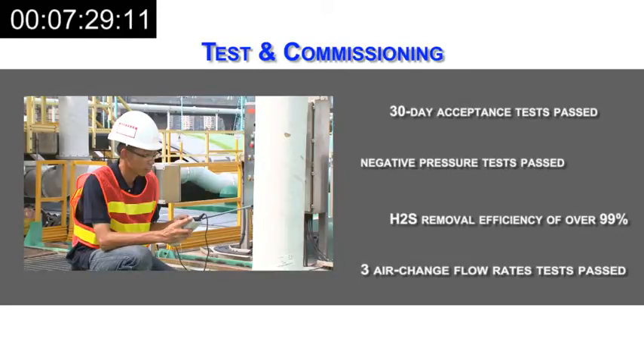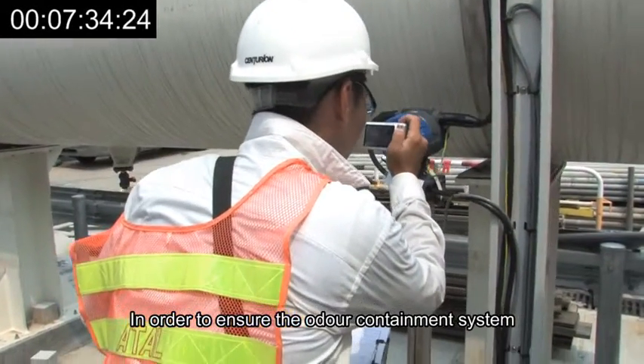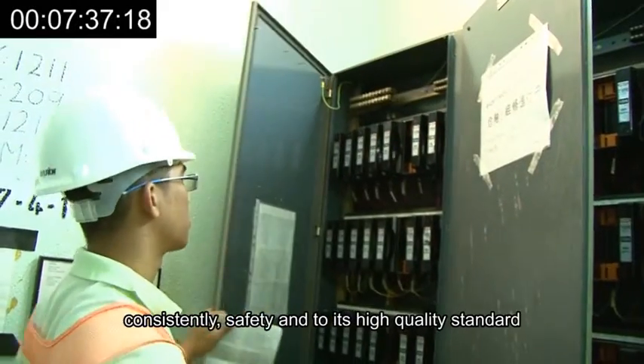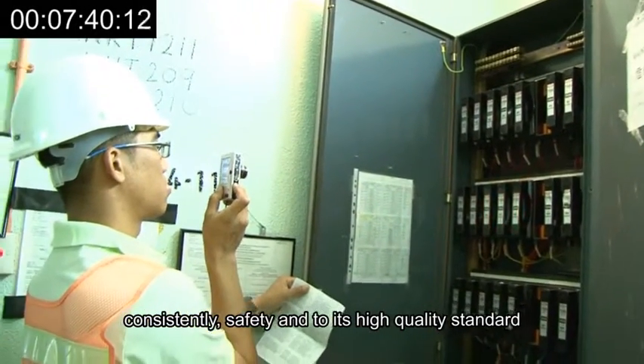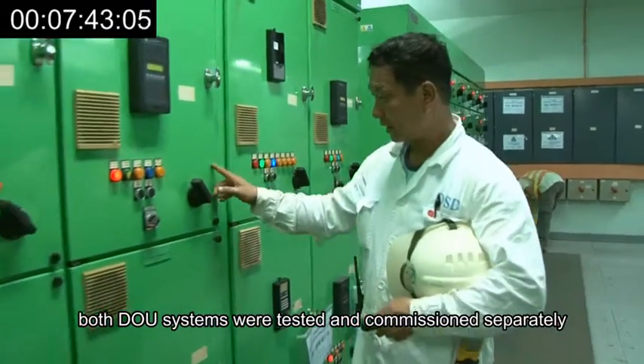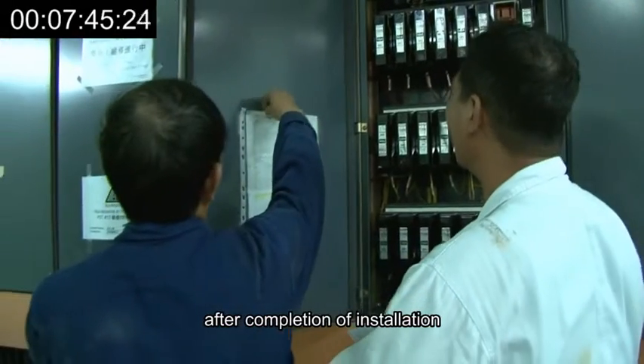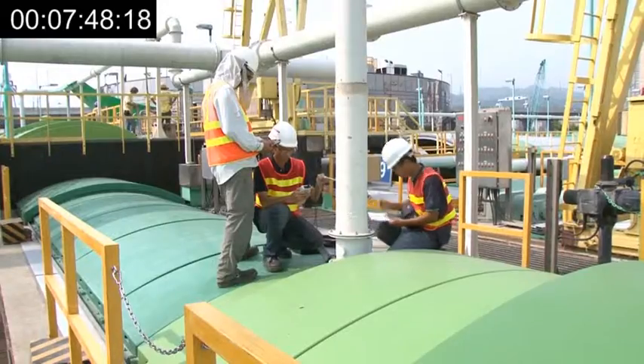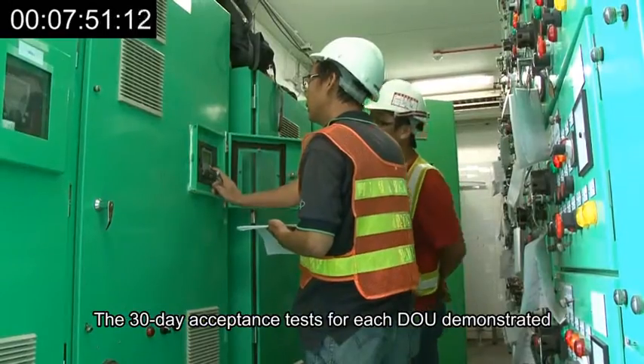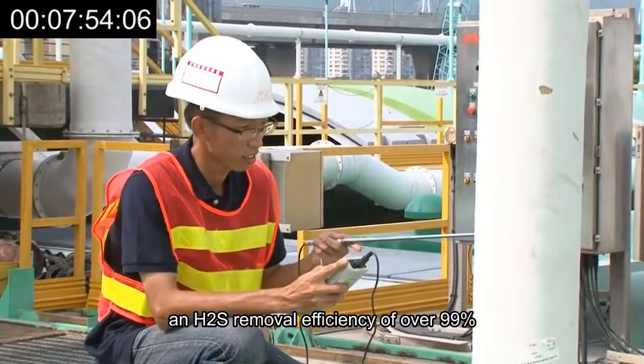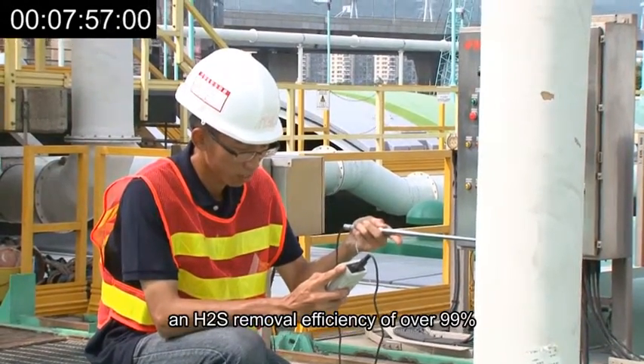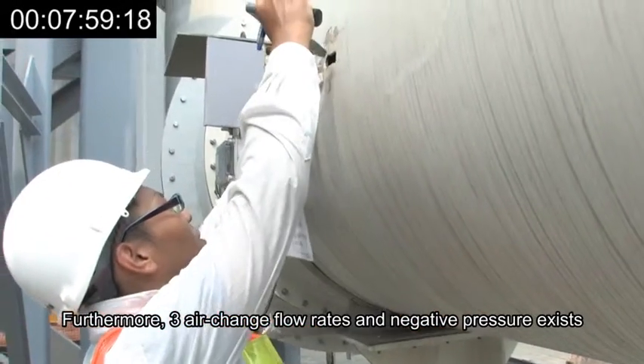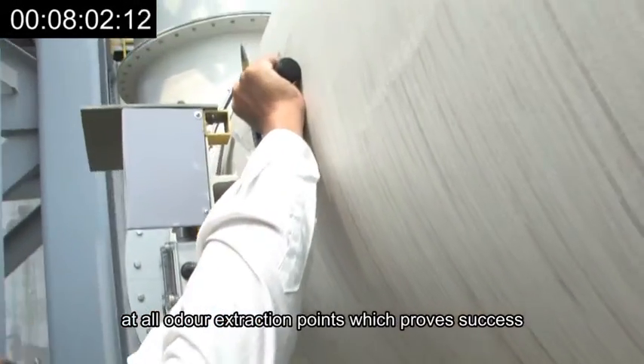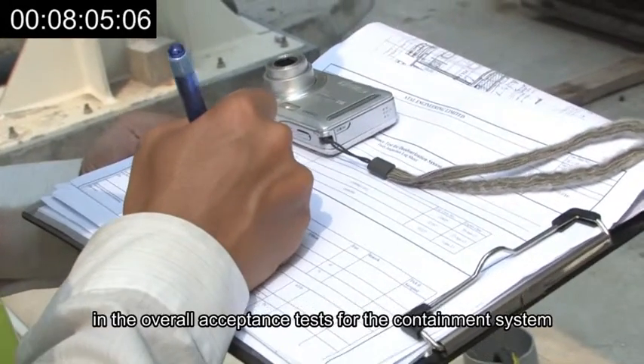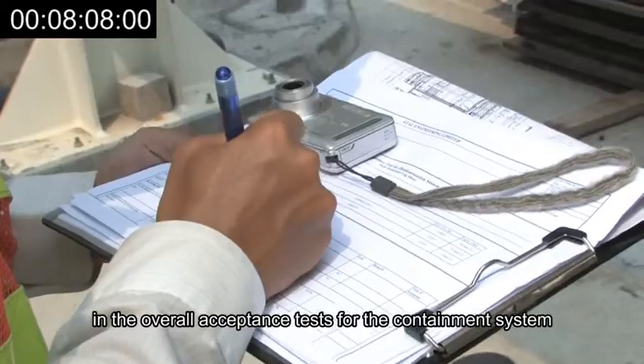Test and commissioning. In order to ensure the odor containment system and DOUs have been implemented reliably, consistently, safely and to a high-quality standard, both DOU systems were tested and commissioned separately after completion of installation. The 30-day acceptance test for each DOU demonstrated an H2S removal efficiency of over 99%. Furthermore, 3 air change flow rates and negative pressure exist at all odor extraction points, proving success in the overall acceptance tests for the containment system.